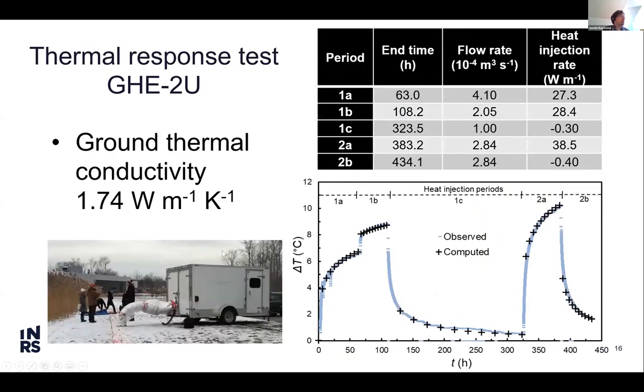So same thing again, a thermal response test was done, bringing this field test unit with the heater in the element, insulating the pipe carefully again, even more than the previous time, learning from our previous mistake. This test was done in the winter. This is just the beginning of the test, at the beginning of the winter, but it was finished by the end of January, where there was about 1 meter of snow on the site.